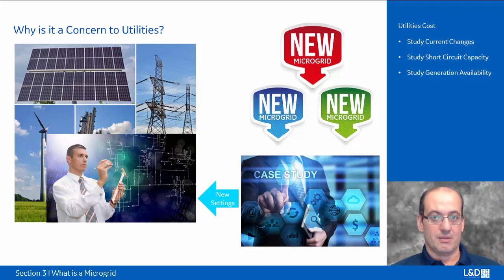If we can find that perfect microgrid that will never contribute to a fault current, and they don't have to change their system, that will be an ideal situation. But the reality of the matter is, if we define our microgrids to be up to 10 megawatts and above, every additional source will have a cost impact to the utility.